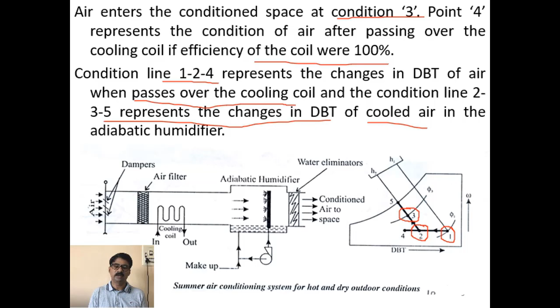Therefore the condition line 1 to 4 represents the changes in DBT of air when it passes over the cooling coil, and the condition line 2, 3, 5 represents the changes of DBT of the cooled air in the adiabatic humidifier. So the actual process will be from 1, initial condition atmospheric air, after the cooling coil the condition will be 2, and after adiabatic humidification, the condition will be 3. So the air enters into the air conditioned space at condition 3.